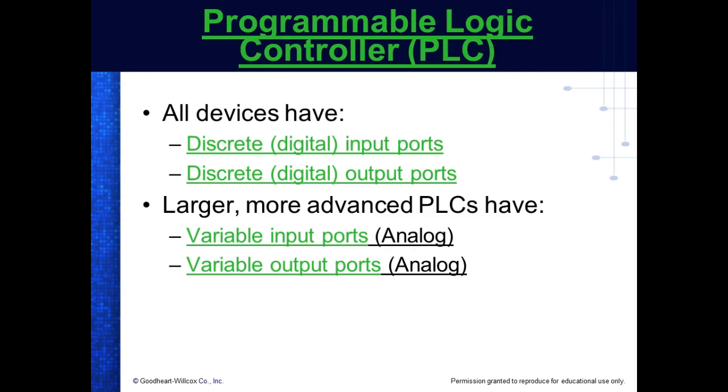So I think this guy right here has 2 analog inputs on it. And the 1200 right here has 2 analog inputs. They're labeled A right here at the top. So that's built into this PLC. These guys don't have an analog output, but this one does, which means it can generate an analog signal, like to control speeds or control intensity. But you had to get that as an option. It comes with 2 analog ports on it, but the analog output you have to add as an option.